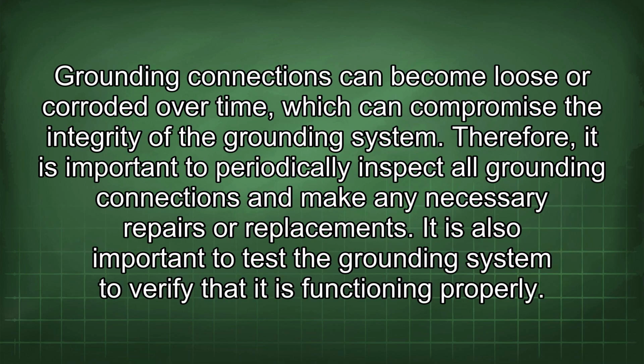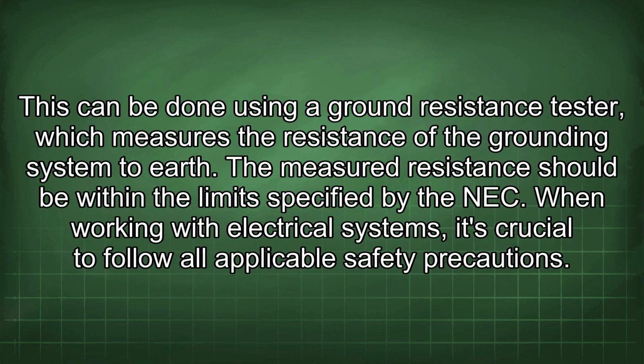Grounding connections can become loose or corroded over time, which can compromise the integrity of the grounding system. Therefore, it is important to periodically inspect all grounding connections and make any necessary repairs or replacements. It is also important to test the grounding system to verify that it is functioning properly. This can be done using a ground resistance tester, which measures the resistance of the grounding system to earth. The measured resistance should be within the limits specified by the NEC.